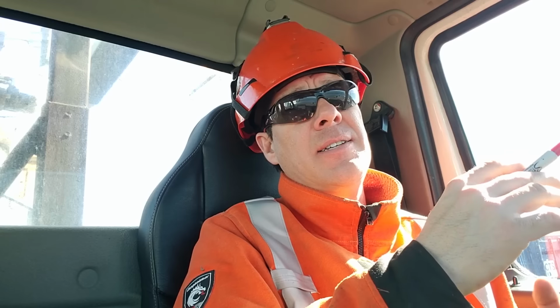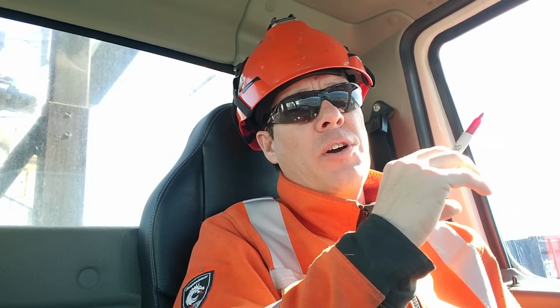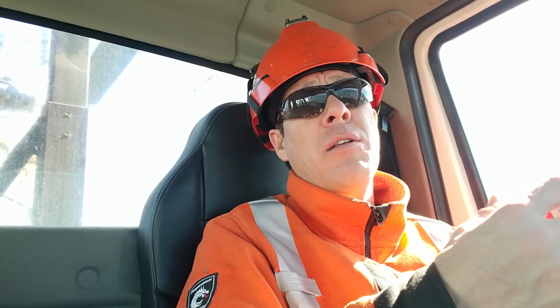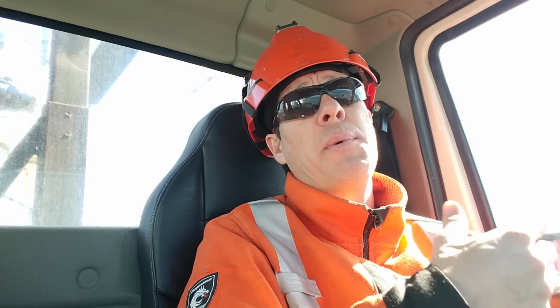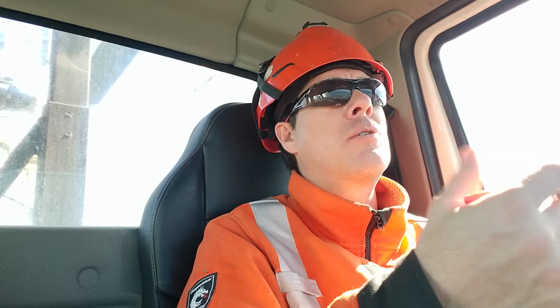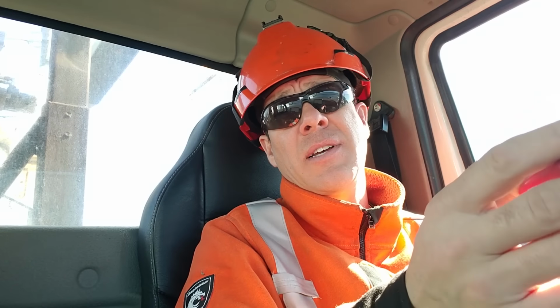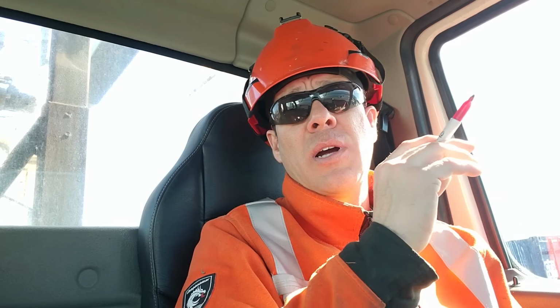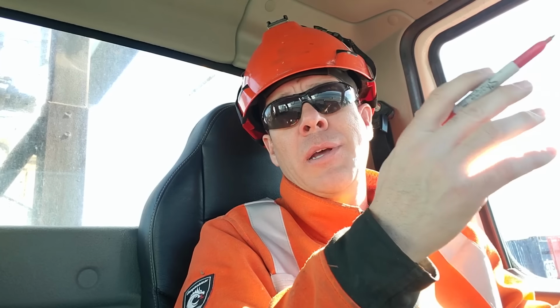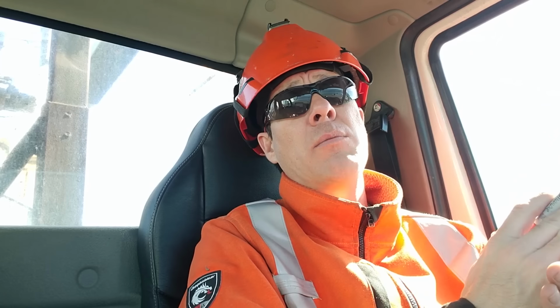Like I said, these things are black and white. It's very important that these are caught. It was caught during the construction before it was even energized, so that's great. Again, that's why we repeat the steps back and forth. Not only do you repeat them, but you don't just mindlessly ramble them off, you got to pay attention to the numbers. You got to make sure you heard the pole number, it's like 12 characters long, so you want to make sure every L, R, 3, 0, B, L, all that stuff is 100% correct.